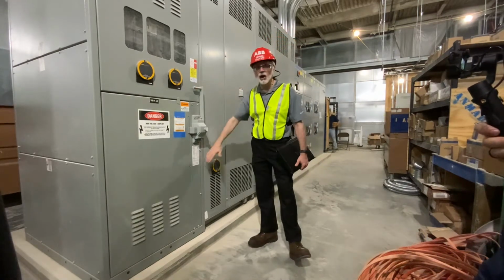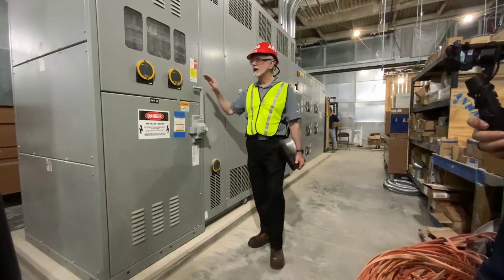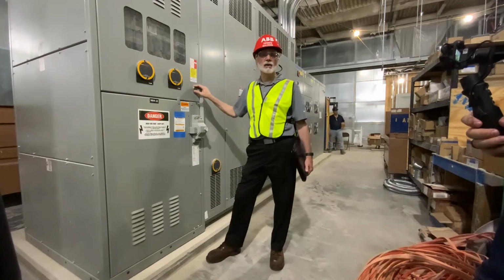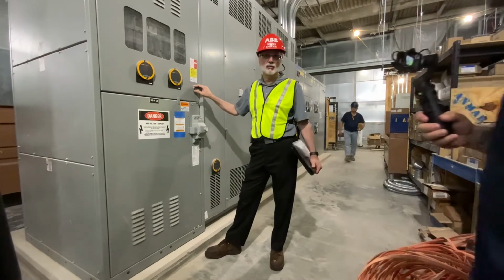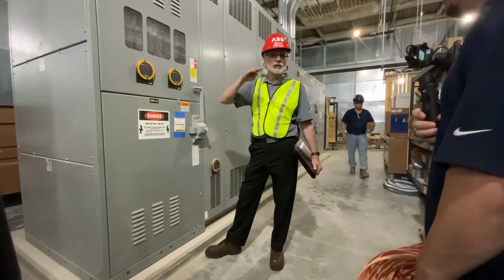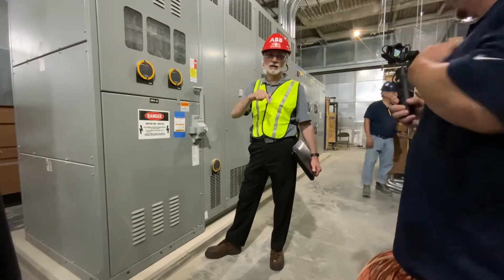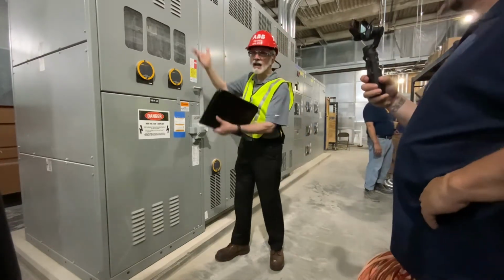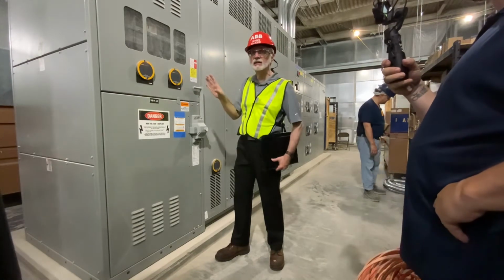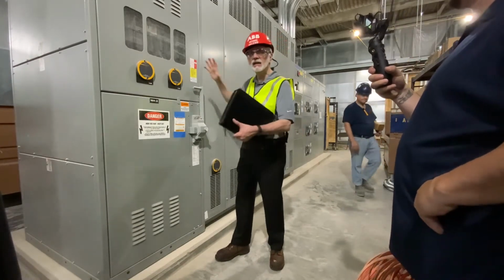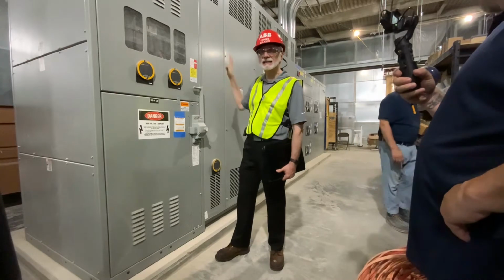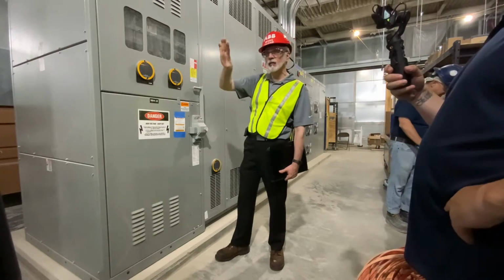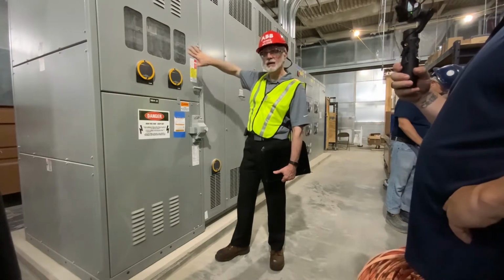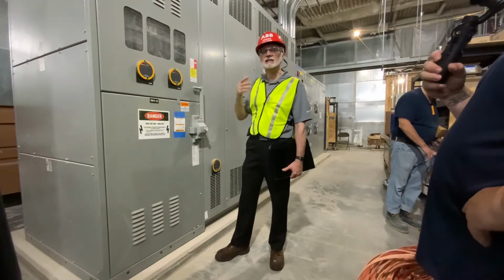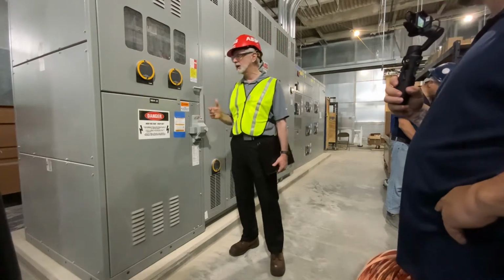This is the on-off lever, quick make, quick break. This is what we call a metal enclosed load break switch. This is not metal clad equipment like we were talking about downstairs, so it does not have the various barriers in between the different sections. It's basically medium voltage equipment inside a box. So if I opened up the front of this and I opened up the back of it, you'd be able to see right through because this is metal enclosed, not metal clad equipment.